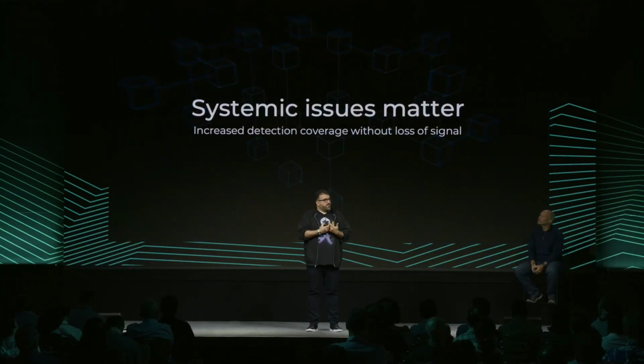The second one is that systemic issues really matter. And this has been the improvement on refinement of how we handle things such as repeat offenders or what I lovingly call slow burn type of issues. This has been critical because we saw that these issues were consuming resources on the data center. These are the folks that actually need to go do the repairs. We were essentially removing capacity from the network that didn't need to be removed, or we were removing way too much instead of actually fixing the issue. And ultimately, a lot of these cases just ended up in no fault found type of repairs. We saw this mostly around optics and certain temperature anomalies.